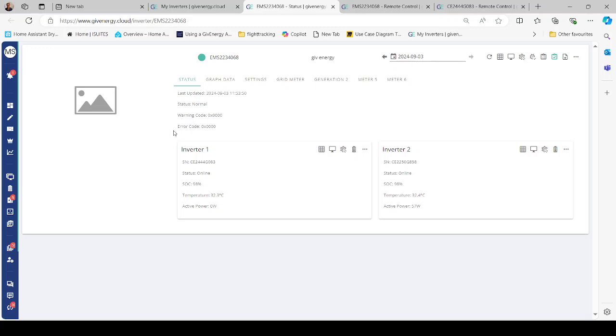Error codes. If your status is warning, you'll normally have an error code in here. There'll be something like 8002. It's just a warning to tell you that one of your inverters is having problems. Could be an overvoltage problem, anything else along those lines. And really, you just need to go and look at the inverter to see what the error is. You know how to work with inverters, so you would know how to rectify them. A word of caution: if you need to do a calibration or charge or discharge the battery, you have to put the EMS into a waiting stage.